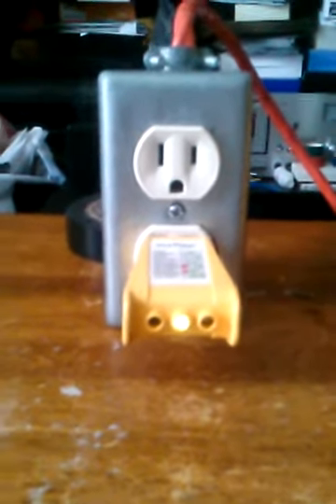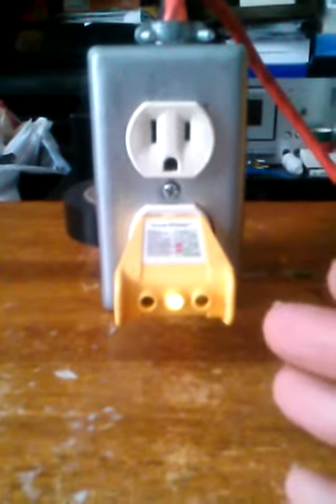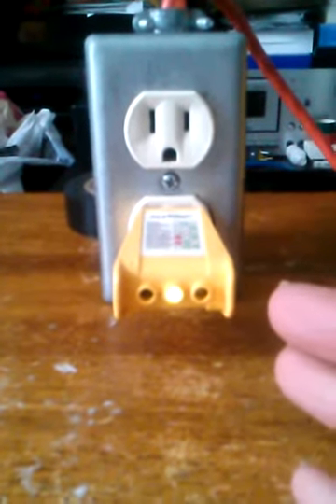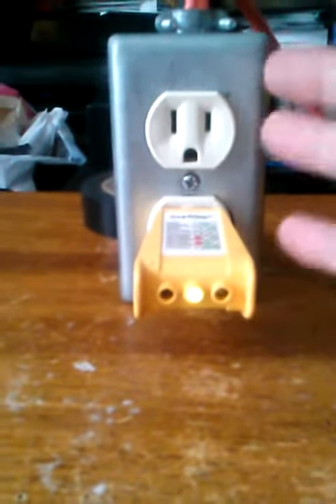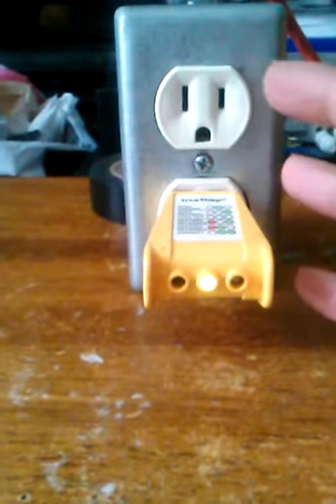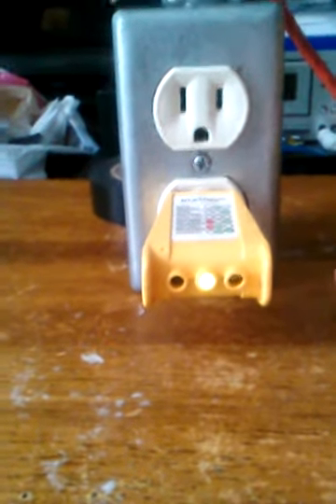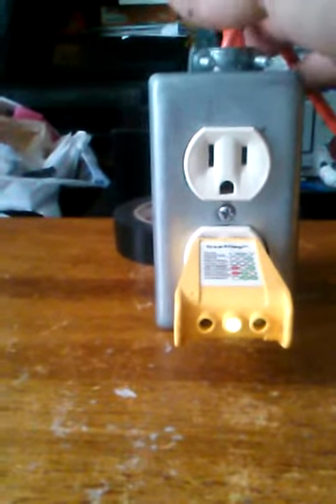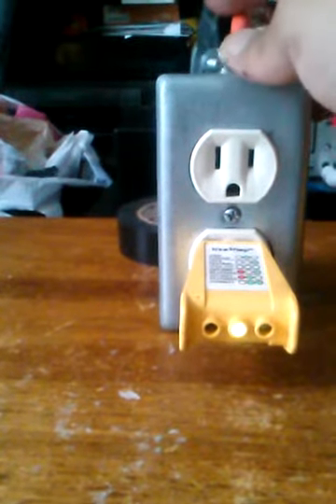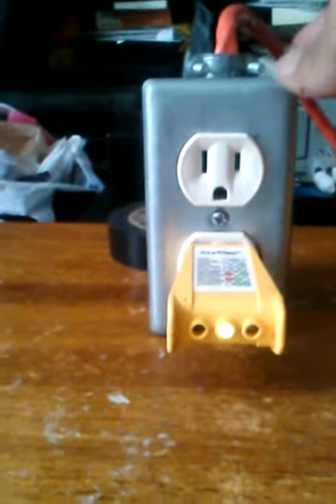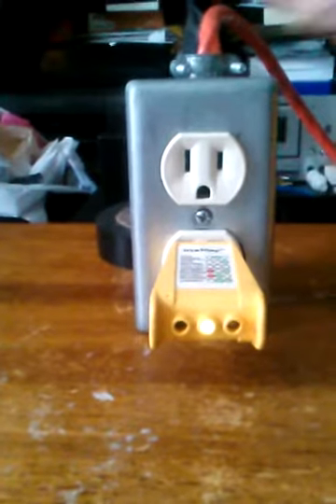Now I just disconnected the ground just for demonstration purposes. You may come across the situation where you're in a house, an apartment, or a building that you're renting or own, and you happen to have a receptacle that has the 3-prong outlet and it's not grounded for whatever reason, either the shielding, which some older buildings have, which is called armor clad, or armor clad AC or BX cabling, which has that steel or aluminum mesh, which also acts as a ground as well.